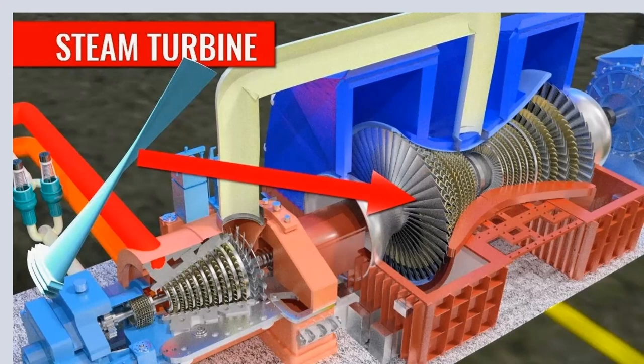As the pressure is reduced, or the temperature is reduced, or both, the volume increases, so you have bigger and bigger blades. When it comes out the other end, it's low pressure steam, and it comes through the yellow header down to the middle of the low pressure turbine. Typically you have it in two directions so you don't place a lot of force on the shaft. It expands again and goes out the bottom as very low pressure steam. There's a condenser down below that condenses it back to water, and you pump it back up again.